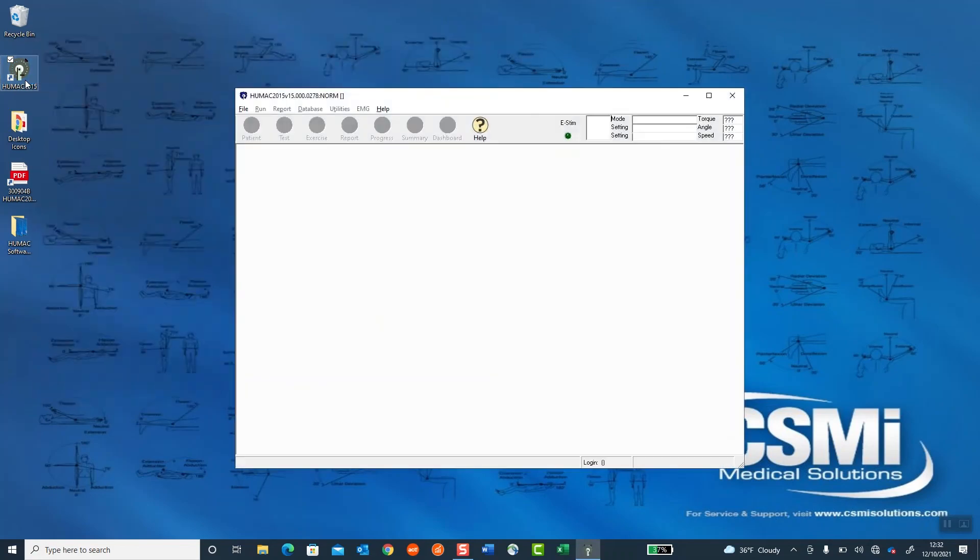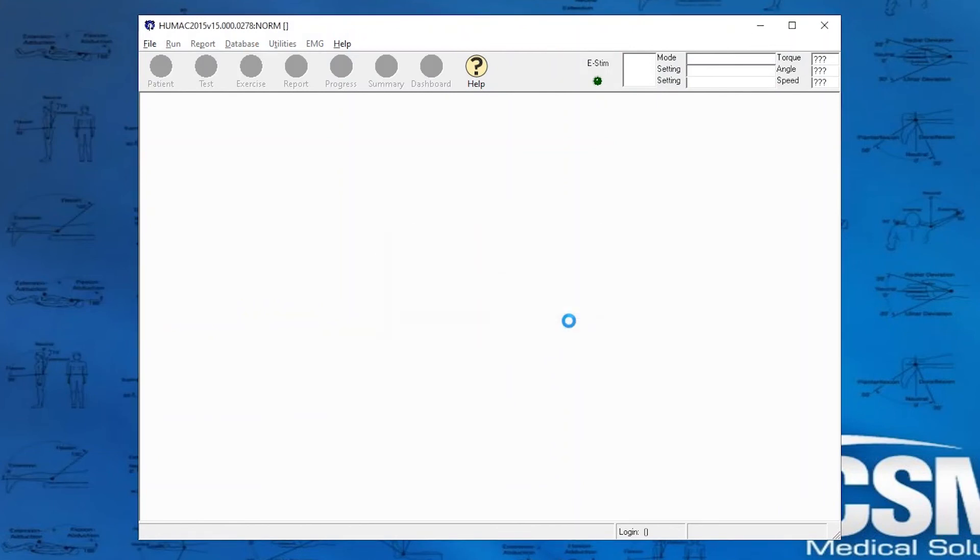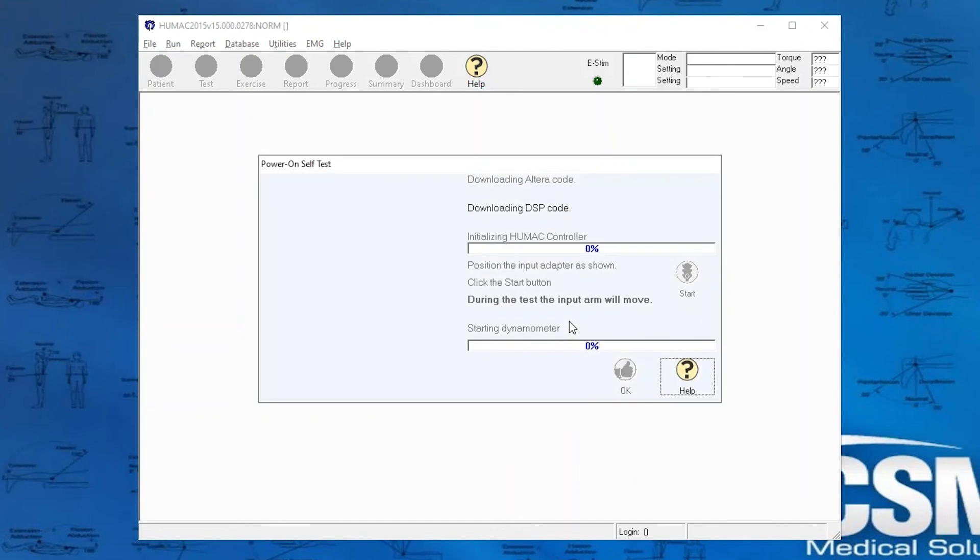And now I'm going to double-click on my HUMAC icon. The system has not been calibrated, so we'd want to run the calibration routine, which is Utilities Calibration. Select OK. The Power On Self Test. It's important during the Power On Self Test that you do not have any adapters in the input arm.